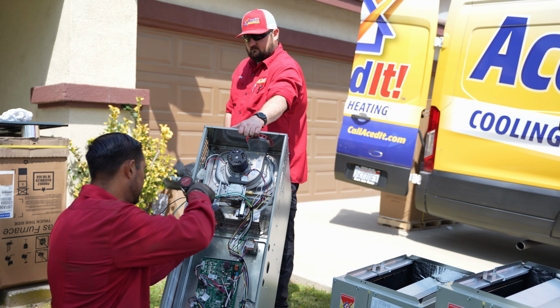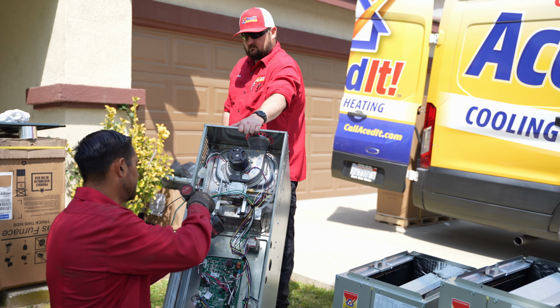What homeowners usually notice is a more stable temperature, quieter operation, longer run cycles, and better humidity control. These systems don't blast on and off as aggressively as single stage systems. The downsides, you do have a higher cost than a single stage unit. There are more complex equipment. But for most homeowners, this ends up being a sweet spot between comfort and cost. And our final group, single stage systems.